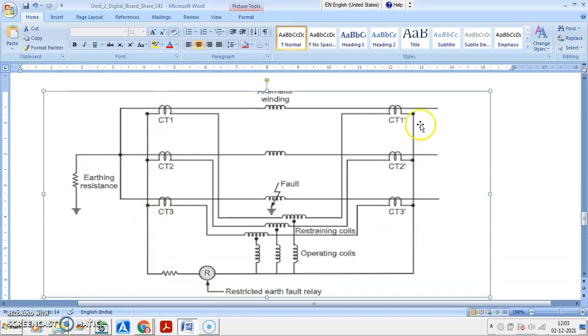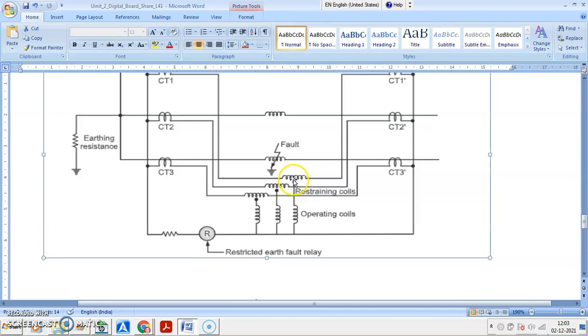These secondaries of all three CTs are connected in star, and this is connected through the current limiting resistor and restricted earth fault relay. The second terminals of all CTs are connected through restraining coils: 1 to 1 dash, 2 to 2 dash, 3 to 3 dash. An operating coil is connected. This is differential protection. So the operating coil is connected here between the neutral point and the secondary terminals of the CTs. You got the connections, CT secondary connections.